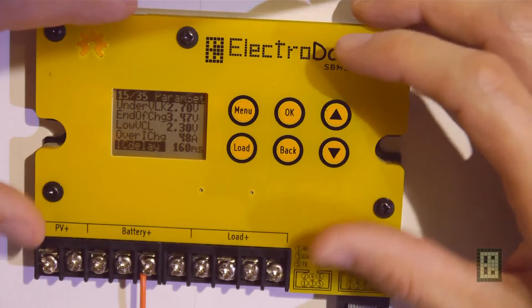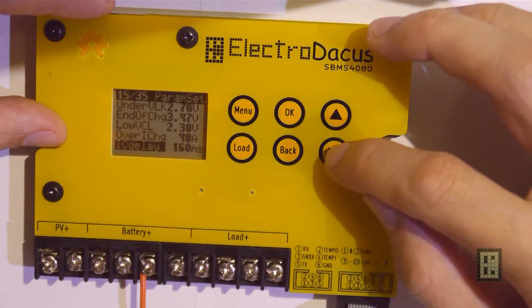And now this is the overcharge current. It's set by default at 48 amps. Of course, this is the 40-80, so 40 amps continuous charge and 80 amps continuous discharge. So the overcurrent is set 20% higher, and the same thing is valid for discharge. It's set at 96 amps, so you can definitely use 40 amps and 80 amps. It's not the limit. The limit is set about 20% higher, and this limit is set in hardware, so the current measurement for the battery is done very fast, so you can, in hardware, not in software, cut the load or the charging if these thresholds are exceeded.